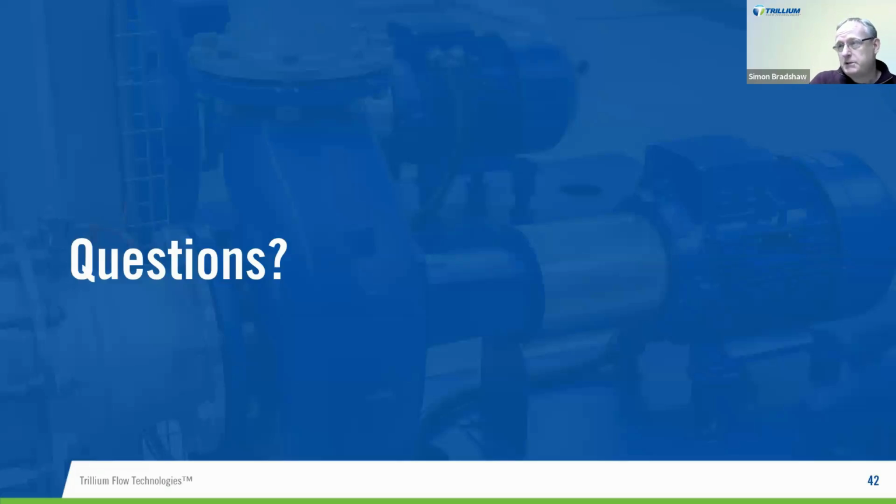When you're talking about a multi-stage pump, you're talking about a seal plan that has something like a pumping ring. You're talking about rotor dynamics and considerations around that. Yeah, your turn down is going to be much less. If you put me on the spot and said a rule of thumb, probably you can turn down to maybe 30 to 40% of your normal speed. And I'm assuming here that we're running at 2-pole speed in the case of these multi-stage machines. So that's where I'd put it if you press me on a single figure. And then you can tell me I'm wrong later.